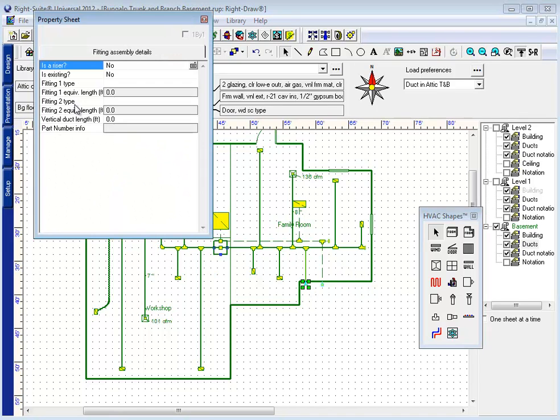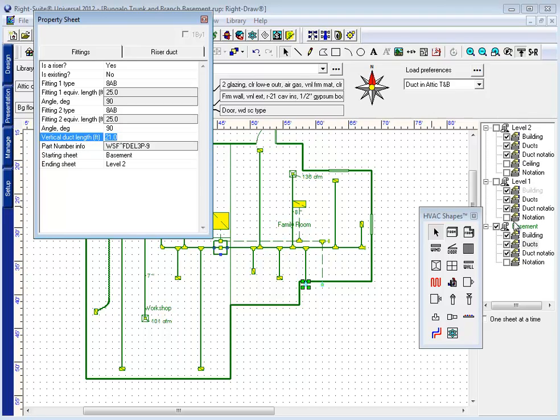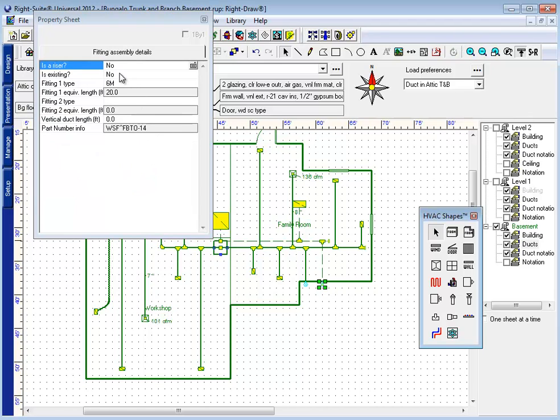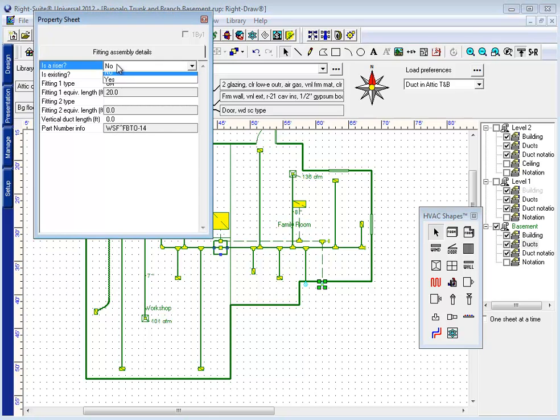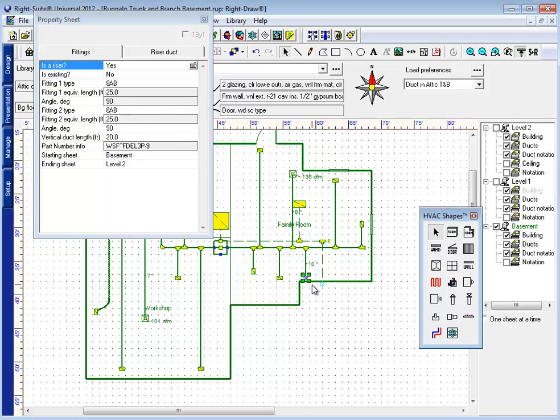This duct is a riser. I need to make sure it's going the right distance to get from my basement up to my level 2, and that distance might be 20 feet. The same for my return as it goes upstairs. Is this a riser? Yes. What distance is it going? I also probably shouldn't run that riser into the dirt.